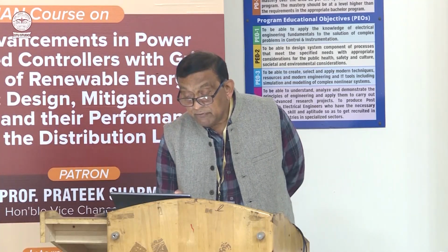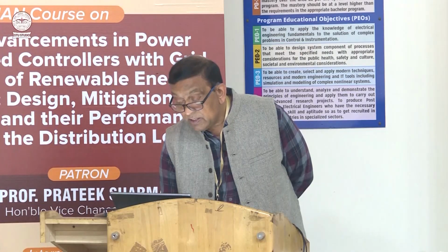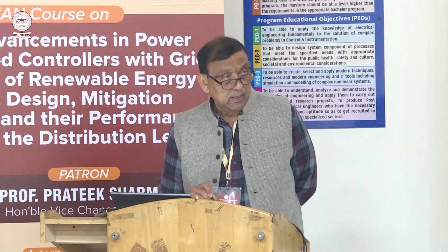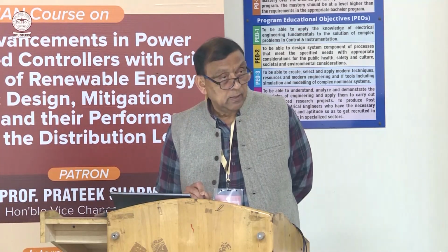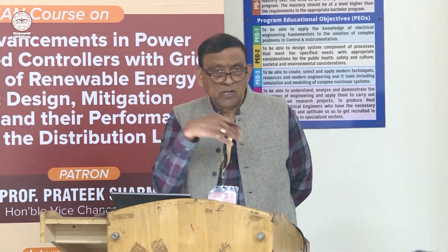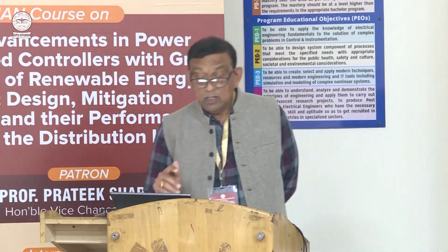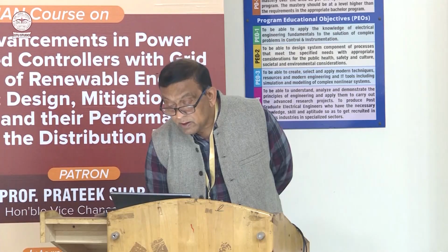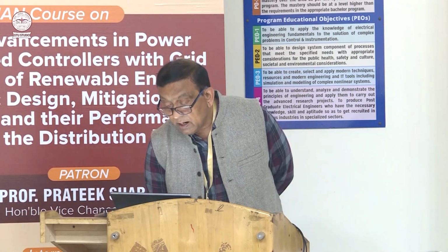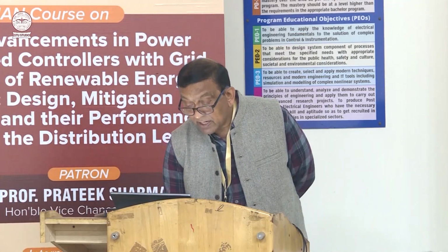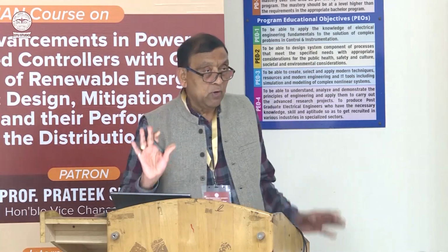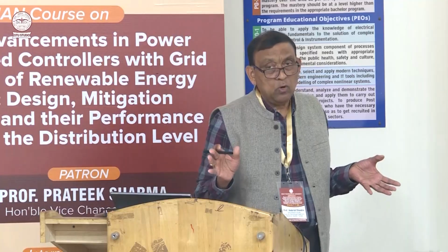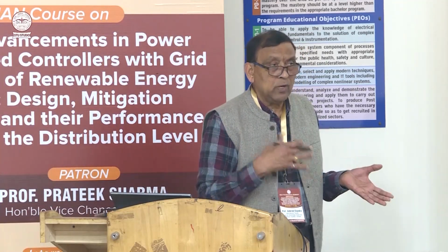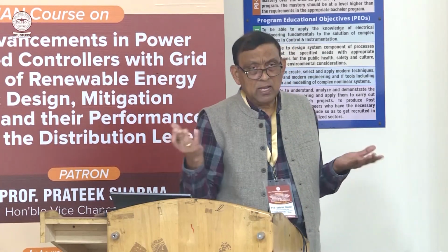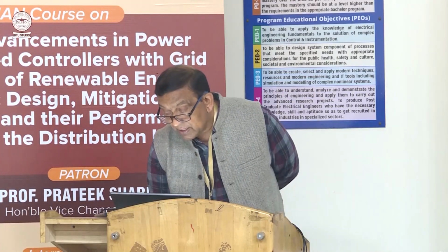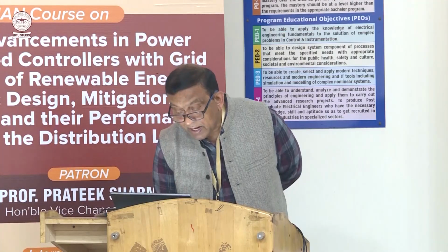So what is basically factor K? It represents the transformer's ability to handle harmonic currents, and they have standardized values. Because you cannot have an infinite number of different transformers, engineers in the industry have put, okay, K factor values may be 4, 9, 13, 20, 30, 40, up to 50. K factor of 1 is for linear load. So you have a simple transformer, balanced system, linear load, so you don't have to worry about harmonics. So you can have K equal to 1, which we generally do even in transmission. While a K factor of 50 is for severe harmonic distortions.